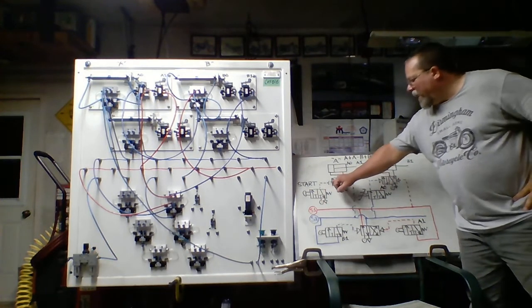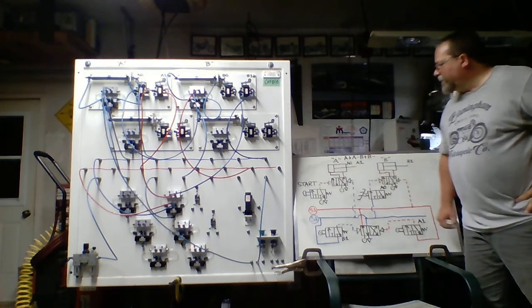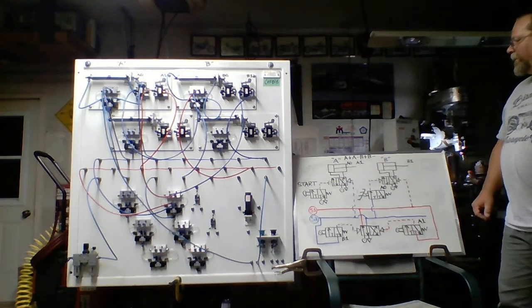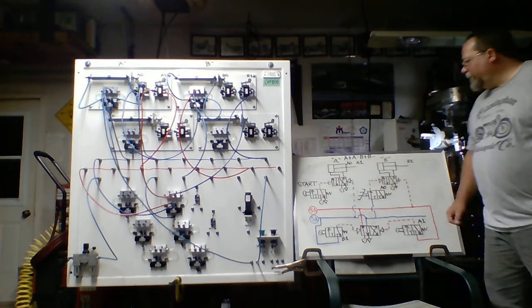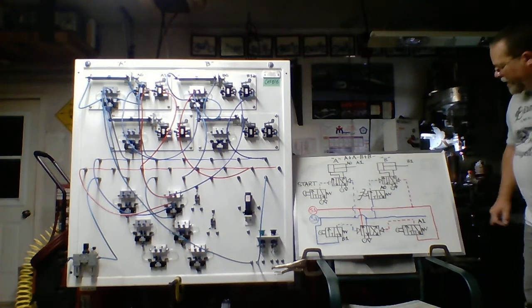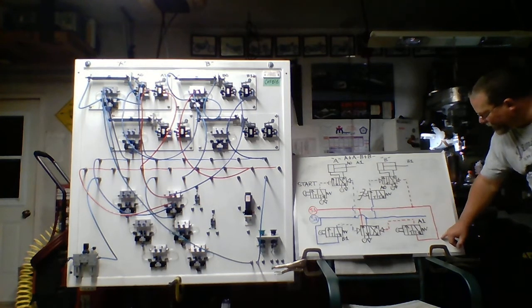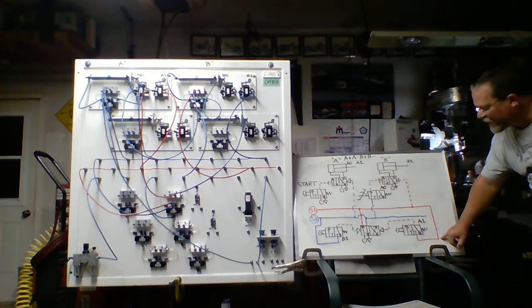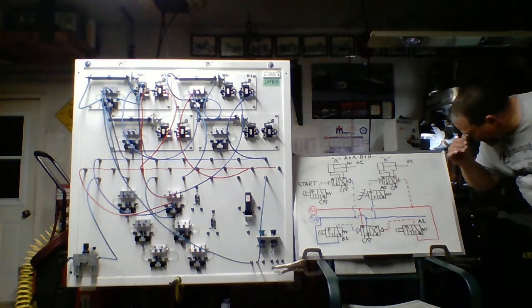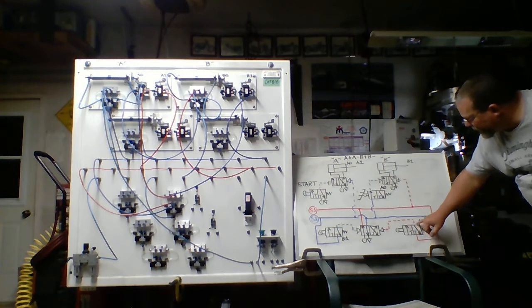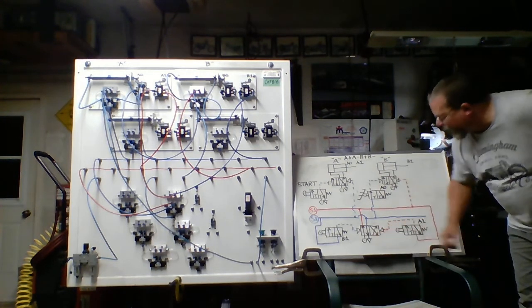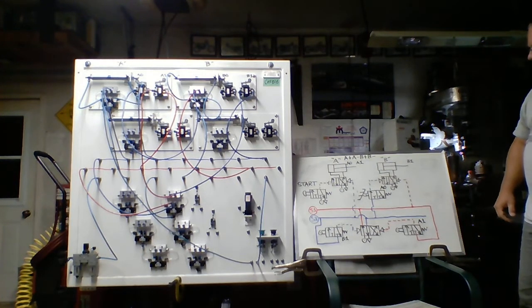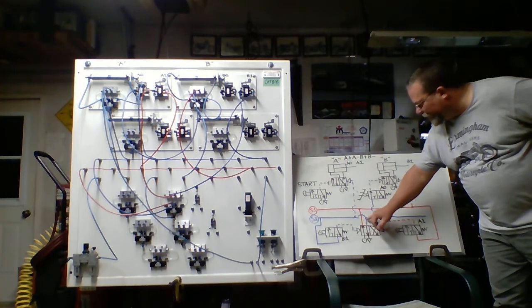So once I push the button and release it, I'm going to pilot this 4-2, which, of course, will shift. Opens the flow path up to the blind end of the cylinder, cylinder A, which will extend. And when it extends, it will actually shift the limit A1. I placed A1 down here. And if you notice, A1, our supply, is source 1 because source 1 is present at this point in time. So what happens when the limit is pushed or shifted, the signal itself is designed to come over and shift the cascade valve. So now we have energy at source 2.